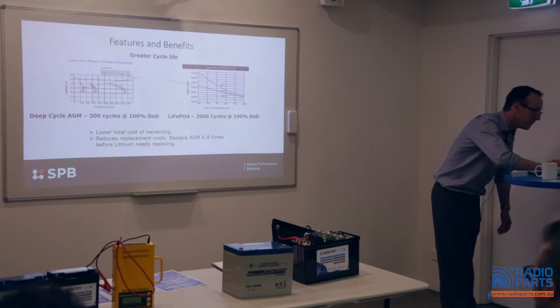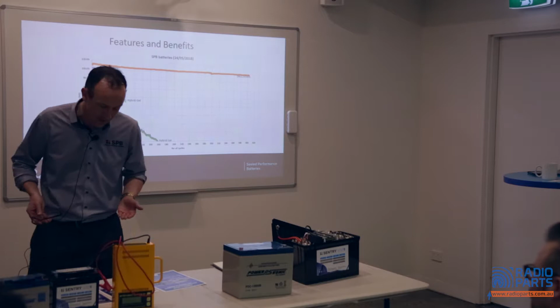It's about capacity degradation. Now, we all know, as I showed you in the graphs before, that depth of discharge and number of cycles, the deeper you drain it down, decreases the number of cycles you can get out of it. But also what happens with lead acid is, the lower you drain it down and bring it back up, the more times you bring it all the way down and lower, it degrades the capacity holding of the lead plates.